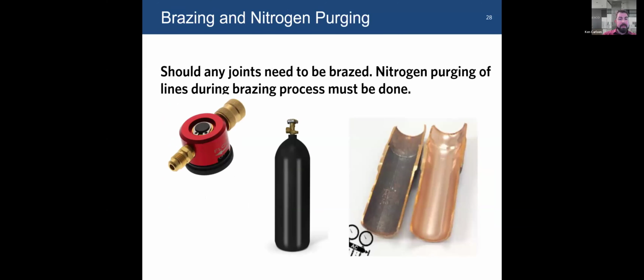Should you have to braze any joints, and this doesn't just go for heat pumps or split systems, this goes for any refrigeration system, you should have a nitrogen purge in that pipe that you are brazing. When you braze, the temperatures of the copper become high enough that it starts to react with oxygen. You get oxidation, you get copper oxide. That's the black on piping. If you've ever seen anything brazed, you'll see this on the outside. This is also on the inside, unless you purge it with nitrogen.